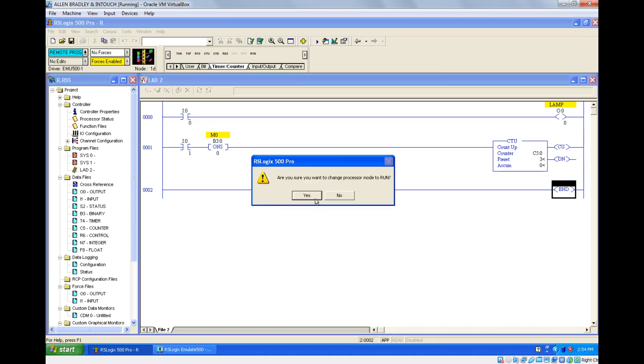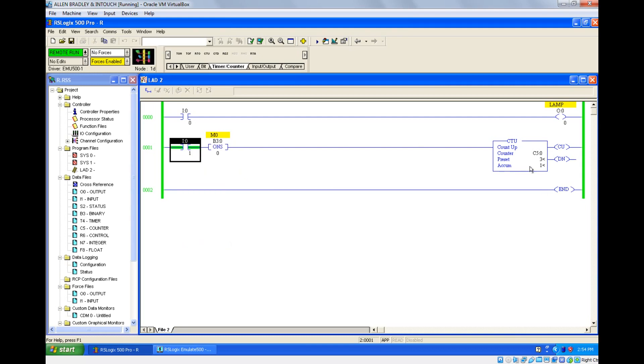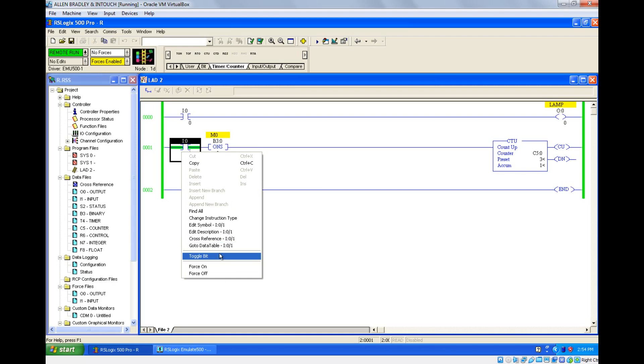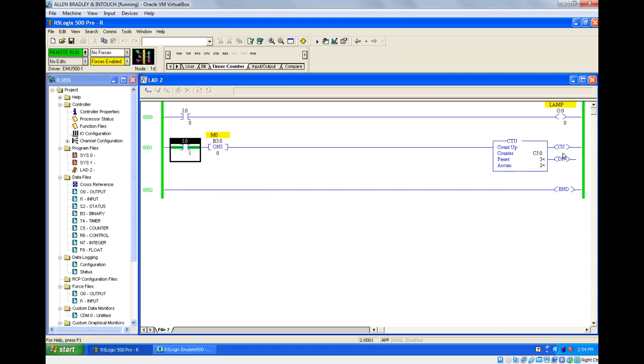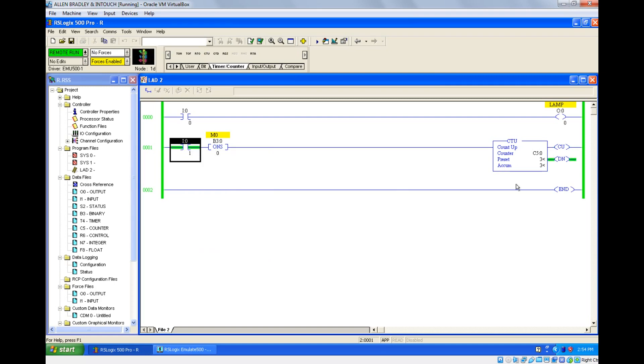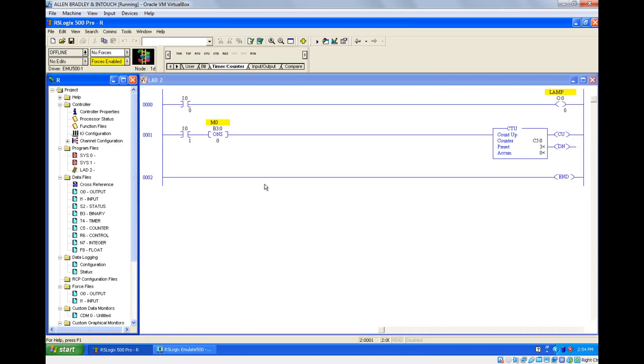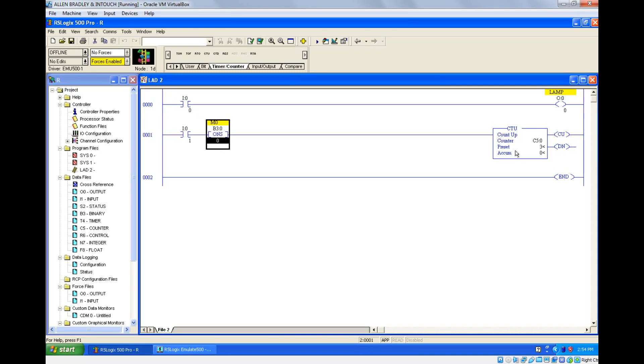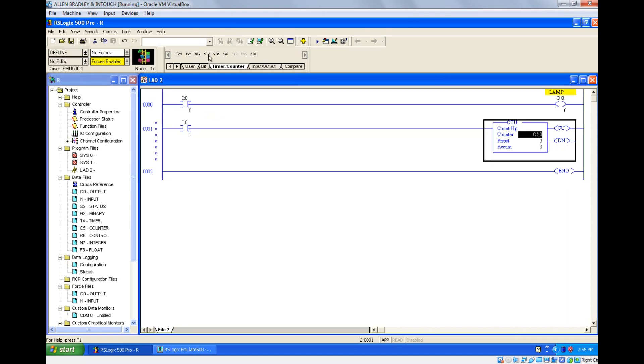I'll give 3 as the preset for the counter. Let's go online and check the counter accumulated value increasing. I'm giving the first pulse — the accumulated value increases to 1 because it got one pulse. The counter doesn't need a continuous pulse; it just needs one pulse to count one. See — I turn on again, count goes to 2. Again — count goes to 3, and the done bit is on. That's how you can use one shot between instructions. Since it is not an output instruction, you must connect an output after it — a coil, counter, or timer.